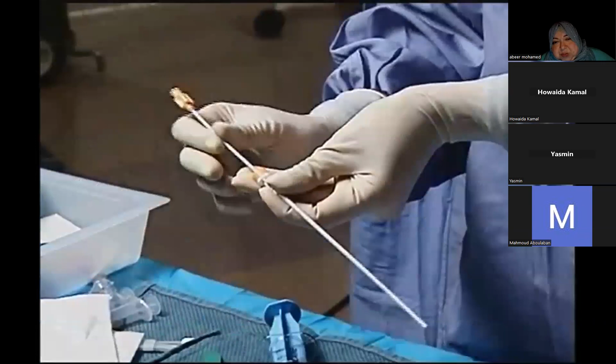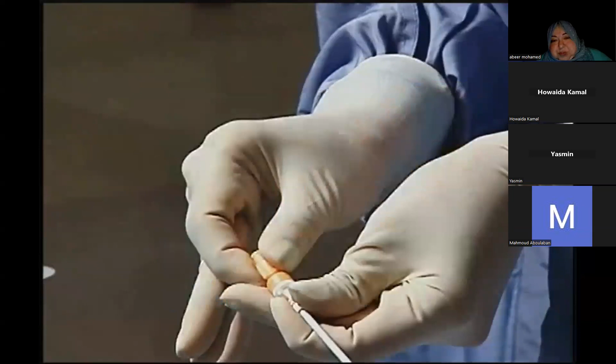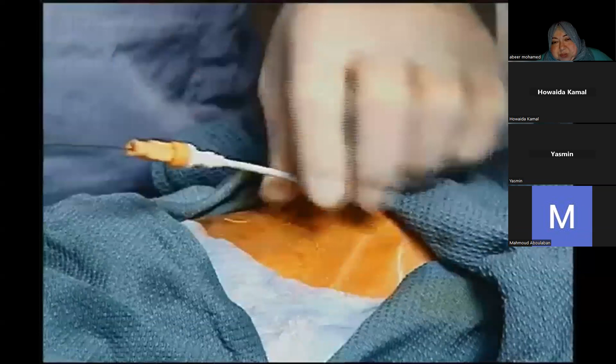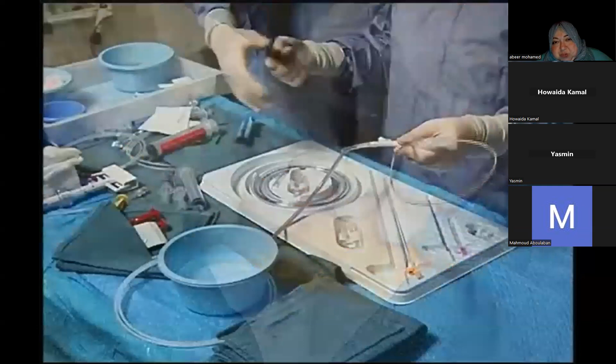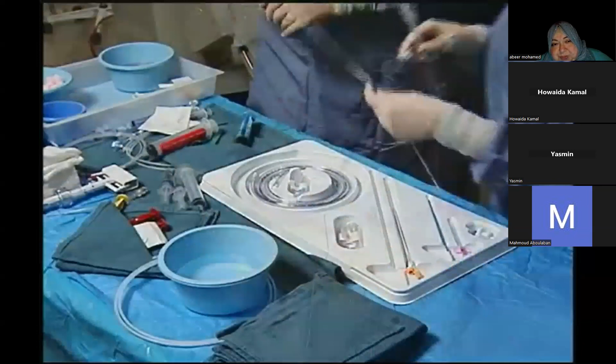Be sure to secure the dilator to the hemostasis valve. This will prevent the sheath from slipping ahead of the dilator, reducing the potential for damage to the sheath and the artery. Place the tapered end of the introducer set over the end of the guide wire. Slip the entire assembly through the skin opening with a rotary motion into the femoral artery. Leave the guide wire, dilator, and sheath in place while the balloon is prepared for insertion. Once you have prepared the balloon, remove the dilator, leaving the sheath in place.